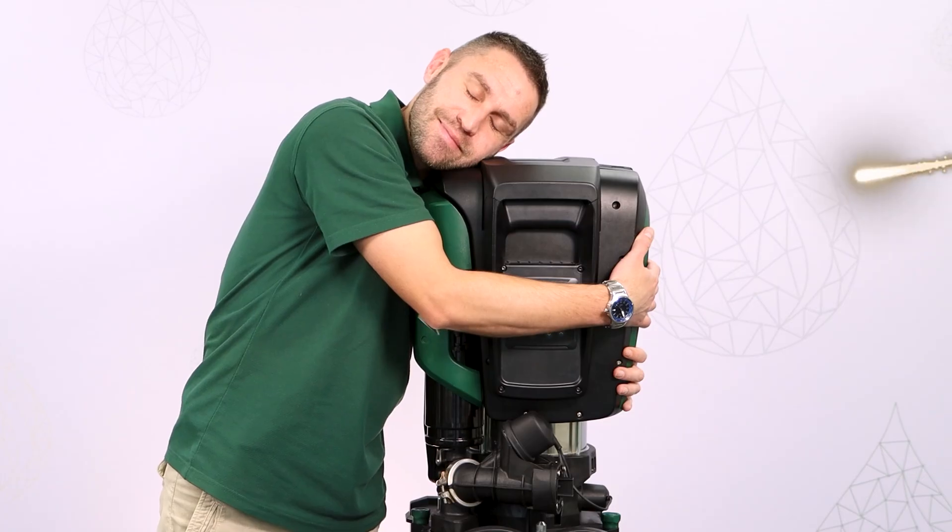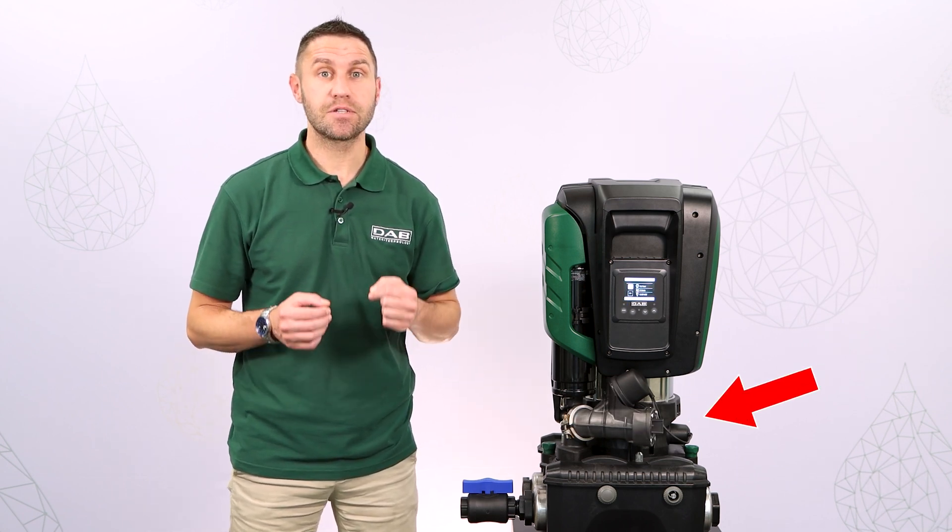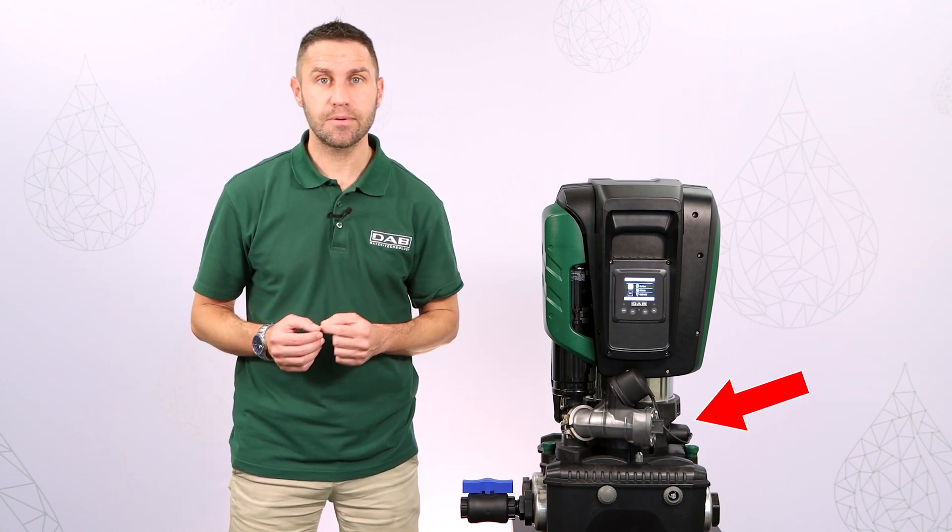With EasyBox Maxx, you don't have to worry about any of that. Like many other things, the valve is already included and integrated into the pump itself, and that same job of inspecting the valve should only take about five minutes. Let's consider the case where your system is not retaining the pressure and the pump is turning on and off too frequently, like so.